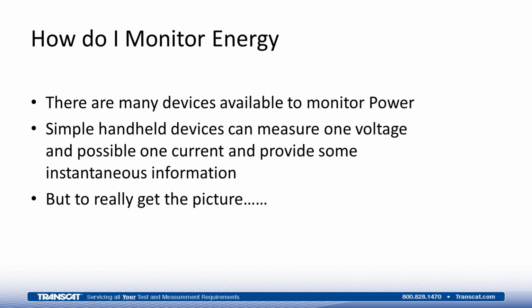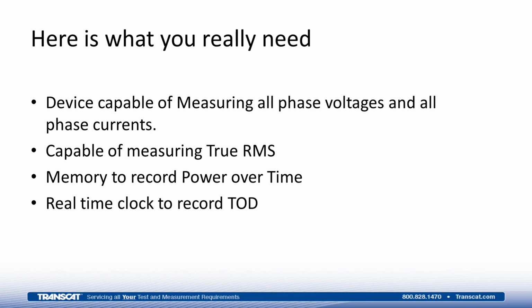Some meters will allow you to calculate the instantaneous wattage from the instantaneous current and voltage. But really, if you want to get the real picture of what's going on, you can't use these types of devices to look at the energy being used. That's strictly the power being drawn instantaneously. To really measure the full system, what you need is a device capable of measuring all three voltages simultaneously and all three currents simultaneously, and able to gather and store that information internally.